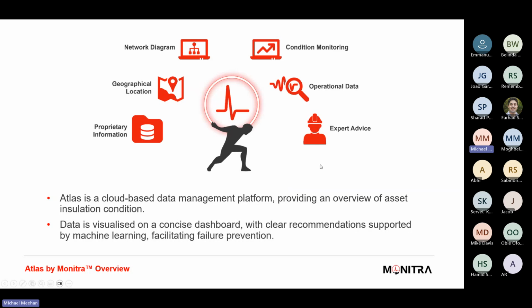Things like that. When it's offline, I'm not going to go into offline today, but there is test equipment where you'll apply a separate high voltage source, and you've got test equipment that you'll hook up and do that measurement. And there are well-established practices on doing that, and it's still worthwhile. Very much one of the best things to do is offline measurements, but you can't just do that every 4 years, 6 years, and think that's good enough. You do need to have the condition monitoring now to be able to have that extra condition visibility. And a way of having that extra visibility is to use data management systems and software.